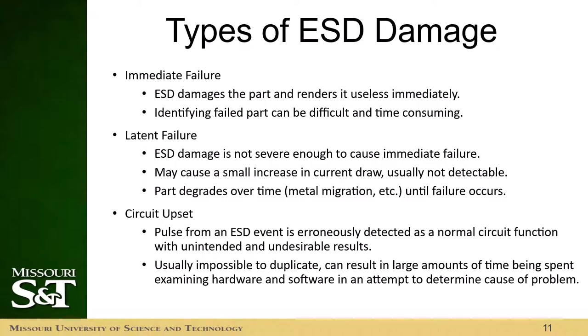There are three types of ESD damage: immediate failure, latent failure, and circuit upset. Immediate failure may be felt as it happens — the ESD event will render the part useless pretty much immediately, though identifying which part actually failed can be difficult and time consuming. Latent failure is also really important: the ESD damage might not be severe enough to cause immediate failure, but can lead to a failure happening later down the road. Something might be completed and working fine, then sent off to the next step, and all of a sudden something fails — when in reality it was an ESD event that caused that part to fail at a later time.